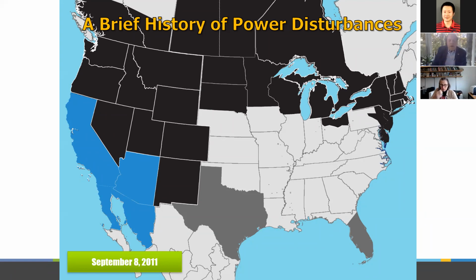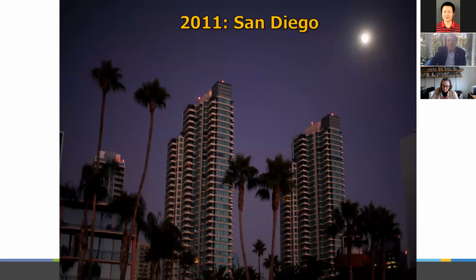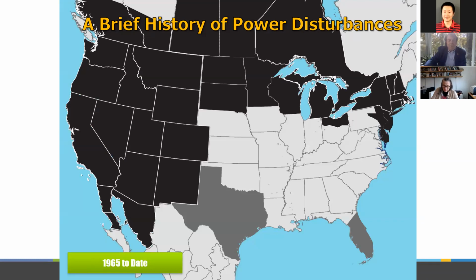A good news story came out of this after we put the phase angle measurement units, the PMUs, in place. It took us about 3 months to get to the sequence of events following the August 14th, 2003 blackout. It actually took 6 hours for Bob Cummings to come up with a sequence of events for this cascading failure. That's San Diego with a full moon, just like New York's full moon.